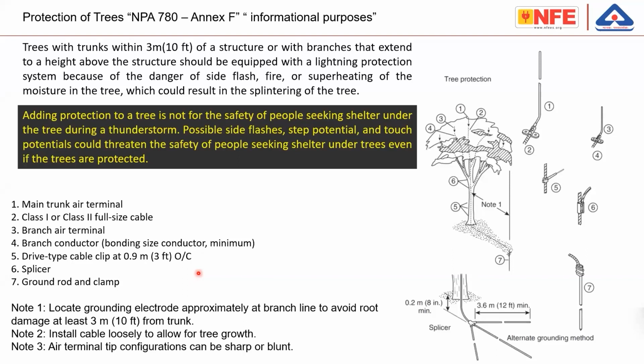What is written? Trees with trunks within 3 meters, 10 feet, of a structure, or with branches that extend to a height above the structure, should be equipped with a lightning protection system, because of danger of side flash, fire, or superheating of the moisture in the tree, which could result in the splintering of the tree. So this is to protect the tree.